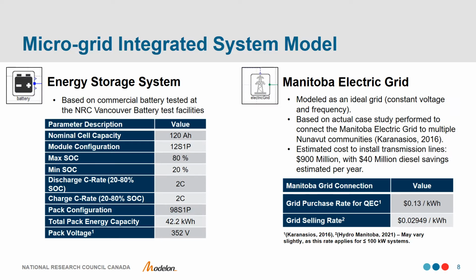The energy storage system was modeled based on a real-world battery system previously tested at the NRC Vancouver's battery testing facilities. The pack modeled had an overall capacity of 42.2 kilowatt hours with a maximum 2C charge and discharge rate and a min and max operating point of 20 and 80% state of charge respectively. The grid was modeled as an ideal grid with constant voltage and frequency. The details surrounding the grid are based on an actual case study that was performed to look at the economic feasibility of connecting multiple Nunavut communities to the Manitoba electric grid.